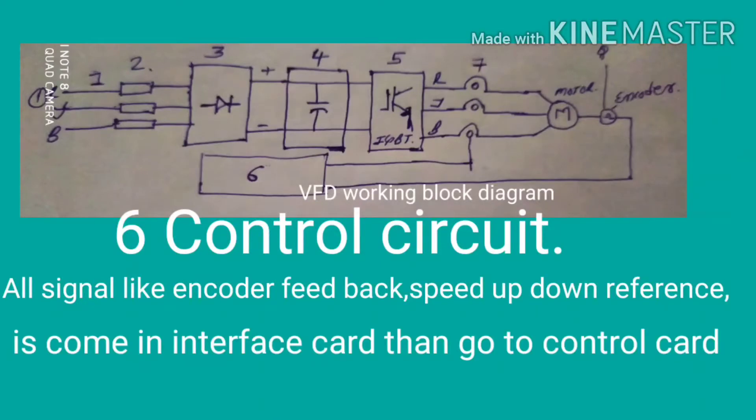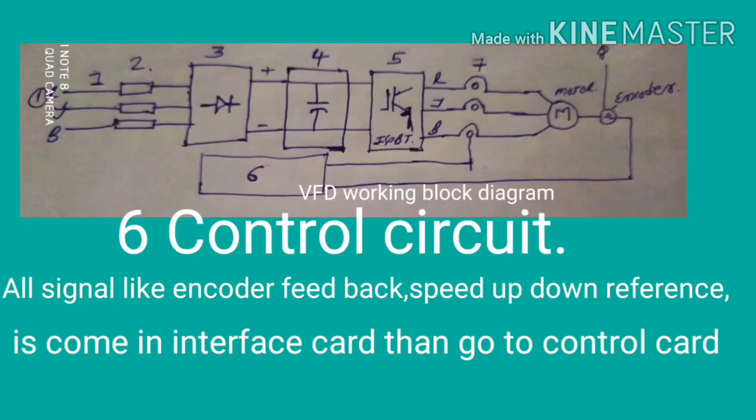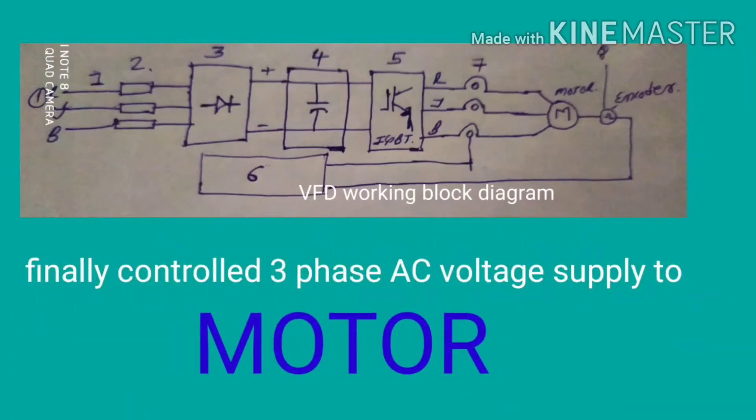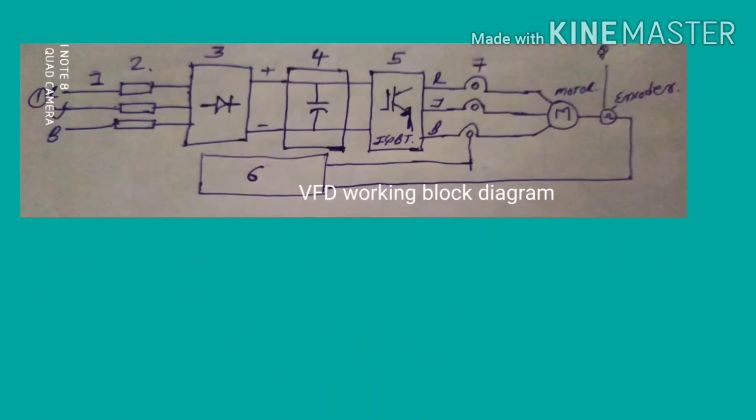IGBT switch on and off is managed by control section. Here trigger card, interface card, and control card is mounted. All signal lines—encoder feedback, speed up, down reference—come in interface card, then go to the control card. Finally, control three-phase AC voltage is supplied to the motor. Seventh is the three-phase AC supply and eighth is the encoder feedback signal. Thank you for watching this video.